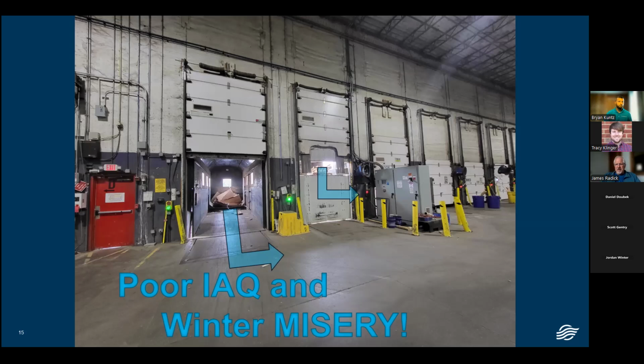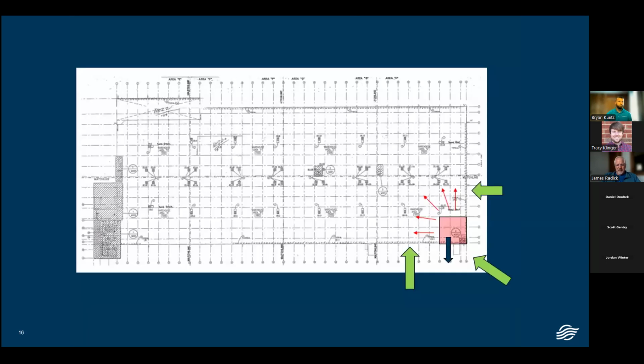And what would happen if you're the poor person going out into this trash compactor, or by that other open door that's partially open to a shredding piece of equipment, and you're in that area? The air is going to take the path of least resistance, and it's going to be very cold, and you're going to have winter misery in those areas. And that's why you end up with uncomfortable areas around the perimeter of a building that's not positively pressurized. That cold air comes in, and it's difficult to get it to mix.